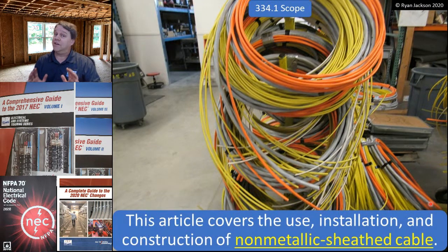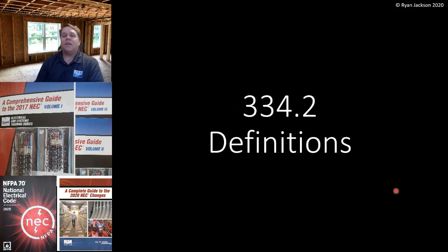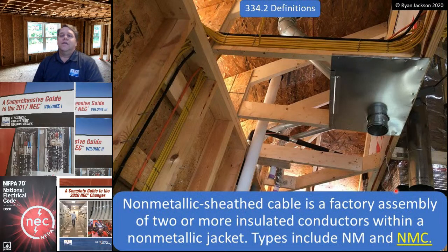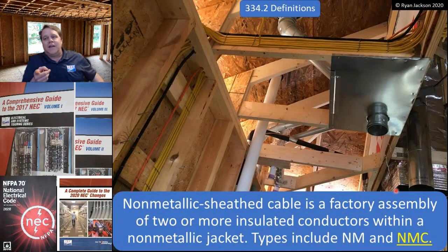So I'm a big advocate of reading the article scopes, even if it's something dumb like NM cable. Article 334 covers the use, installation, and construction of nonmetallic sheathed cable. Nice and easy. Definitions. Nonmetallic sheathed cable is a factory assembly of two or more insulated conductors within a nonmetallic jacket. So, yeah, just what it sounds like. It's nonmetallic. It's a jacket. There you go. The types include NM and NMC.